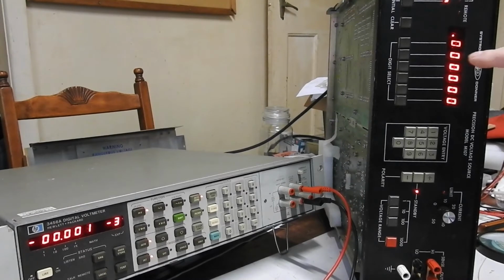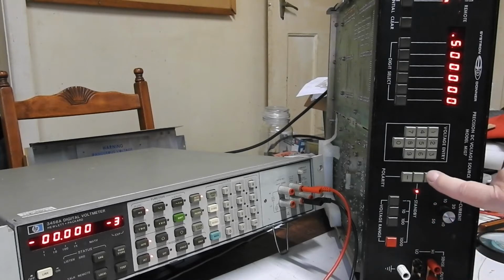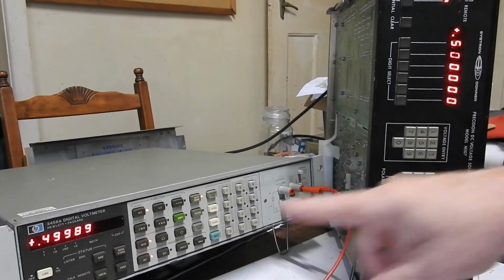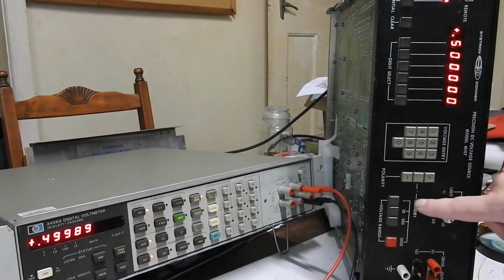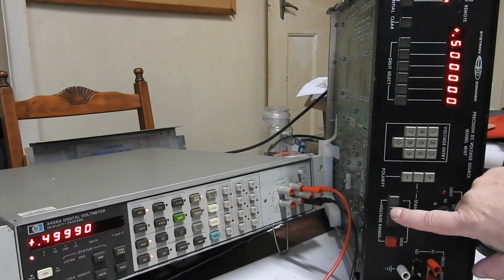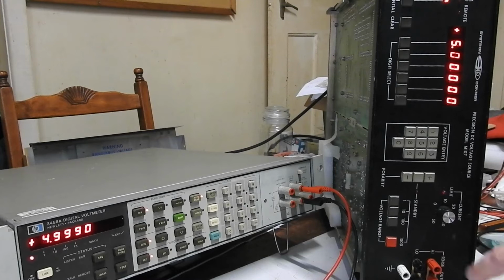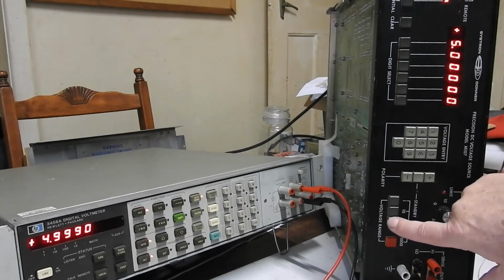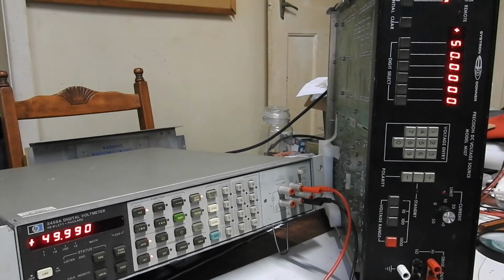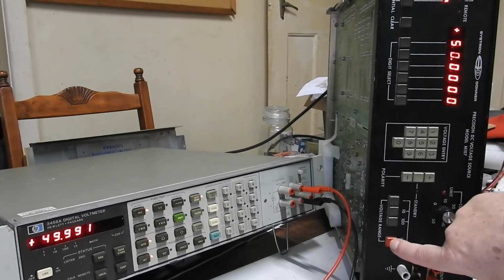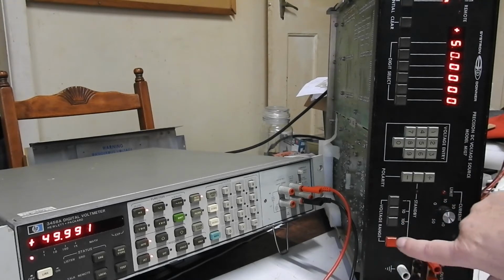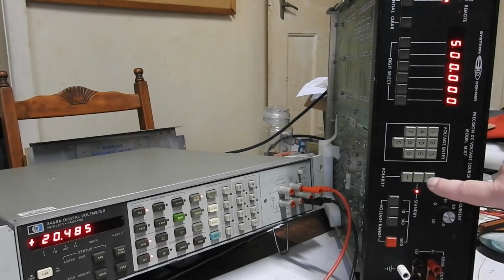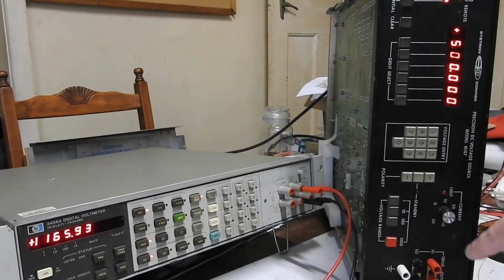Now I'm just going to stick in a 5 to that first position, and then turn on the output, and we get 0.5 volts, very close. On the 1 volt range, on the 10 volt range we get 4.9, on the 100 volt range we get 50, and on the 1000 volt range we should get 500 volts. Dicky switches still, and we're getting overload, so way too much.